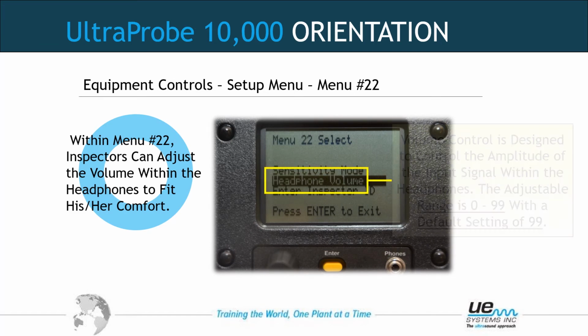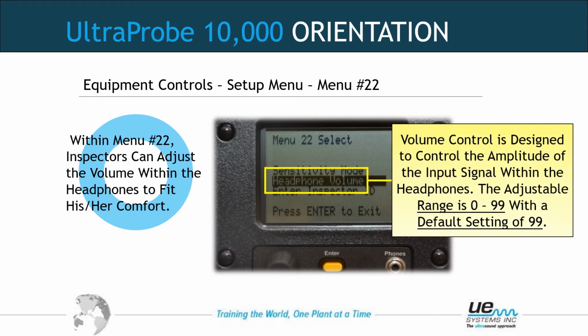Menu number 22, headphone volume. Headphone volume is 0 to 99 on this instrument. Most people don't mess with it. The sensitivity affects the volume, but the sensitivity does not control the volume. Sometimes it's always too loud for certain people, so they will come in and adjust the headphone output volume, and that does not affect the sensitivity of the unit. If you do change this, do remember a person coming behind you may think something is wrong with it if you haven't told them or adjusted it back, and may send it in for repair. Otherwise, leave it at 99 and let the sensitivity affect the volume.